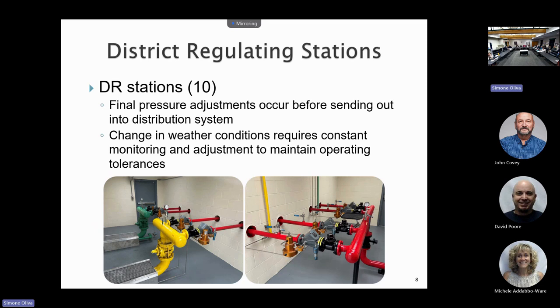These are not automatic adjusting regulators, they're manually adjusted. Every time we see a temperature change of more than 30 or 35 degrees, either we're forecasting before we leave for the day, or our guys - we're blessed to have the people we have in this system - sometimes get up at 6 in the morning before coming in at 7, and first thing they do is pull up SCADA if they've seen a big temperature swing. At 7 o'clock on the nose they're out there, or earlier if needed, making adjustments. You never even know they're doing this stuff in the system. It's constant hands-on evaluation.